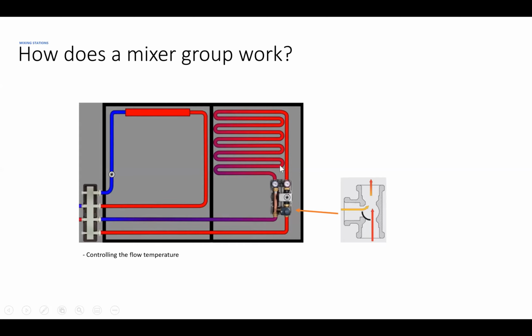Once it gets to a set temperature in that circuit, it uses this little mixer motor to divert the water coming back on the return. So we can have a colder temperature on this circuit than on that one, but we cannot have a colder temperature here than here. That's the point I was making. So we cannot have circuit 1 at a colder temperature than circuit 2. I'm making that point because knowing what to set up on your individual heating circuits is important.